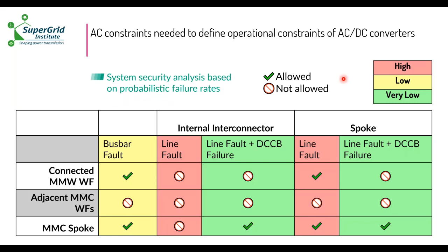So there is one bus bar topology that is called single bus bar, single breaker. So the breakers that you need there are only 3, and with 4 switches, you can perform. Let's say if there is a fault, you will lose power for a longer time, to simplify. If you use a double bus bar single breaker here, you have the same amount of breakers, but you use more switches, so you can reconfigure the bus bar to be faster at the recovery or maybe seamless in case of faults.